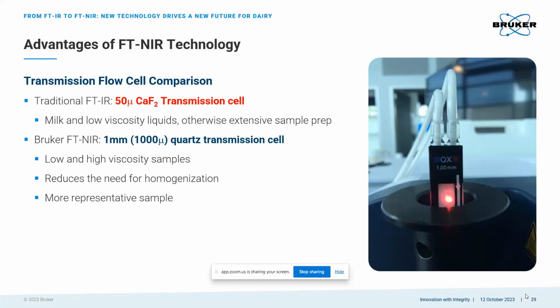So when we think about the main differences in applying FT-IR and FT-NIR for milk and liquid dairy products, we think about the design and procedures for our transmission measurements. Now, the average diameter of the milk fat globules in raw milk is around 4.5 microns, and a homogenizer valve is used to disperse the globules to a more uniform size. So they're usually about 1 micron. And this is done for both IR and NIR instruments in order to increase repeatability and accuracy.